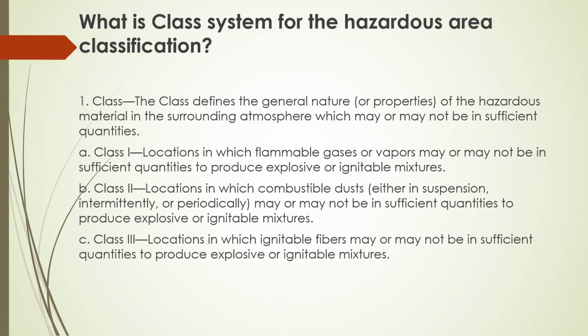Class 2: location in which combustible dust, either in suspension, intermittently or periodically, may or may not be in sufficient quantities to produce explosive or ignitable mixtures. Class 3: location in which ignitable fibers may or may not be in sufficient quantities to produce explosive or ignitable mixtures.